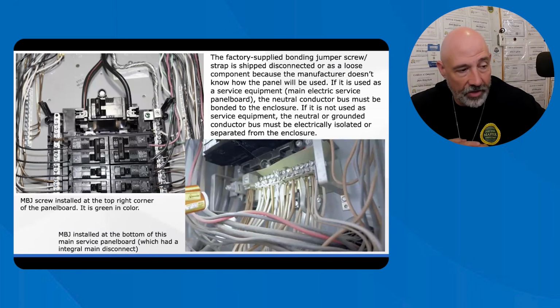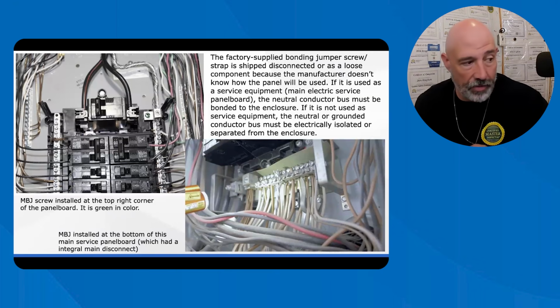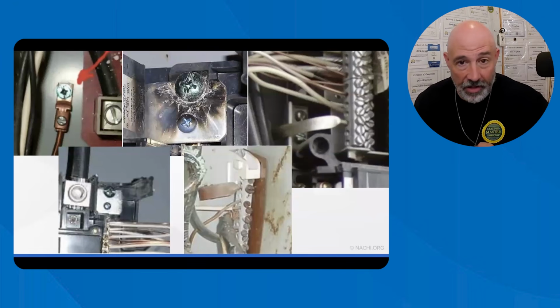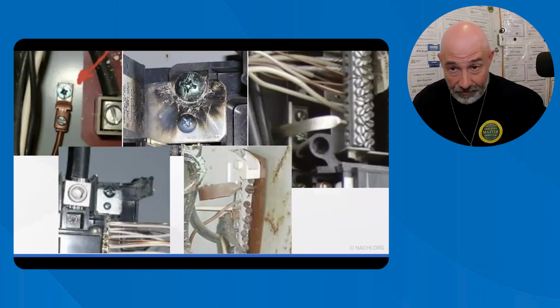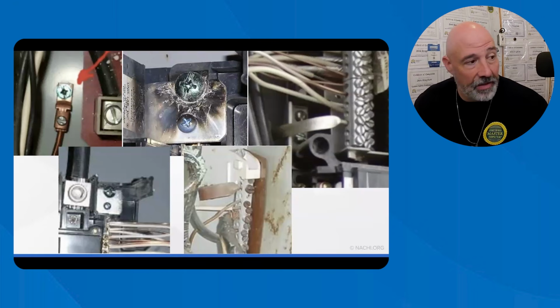You can also see the factory installed there at the bottom. And keep an eye on that too, because sometimes in the sub panels you'll see that jumper, the main bonding jumper wire, connected where it shouldn't be. And the inspector images show several styles of panel board bonding. Some are straps and some are screws, and you can see the little burn there on that one screw. Well, it's because it got energized and it had a place to go.